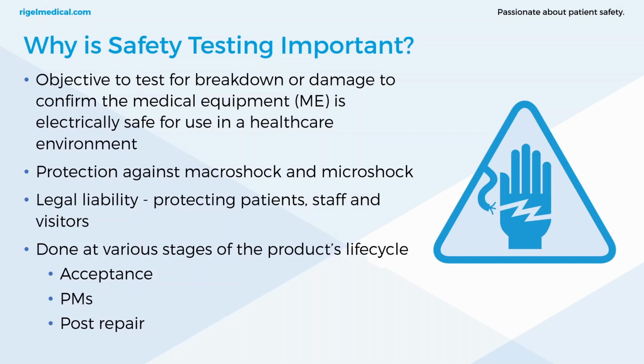So why is safety testing important? The objective is to test for breakdown or damage to confirm the medical equipment is safe to use. Now, as time moves on, medical devices are becoming safer and safer, and failures are becoming less evident. However, performing these tests does protect against any macro shock or micro shock when faults occur with a medical device. It prevents legal liability, it protects patients, staff and visitors, and it's done at various stages of the product's life cycle. So it's done at acceptance. Most medical equipment is widely designed and developed in accordance to 60601 safety standards, and that sets strict rules on the design of medical equipment.